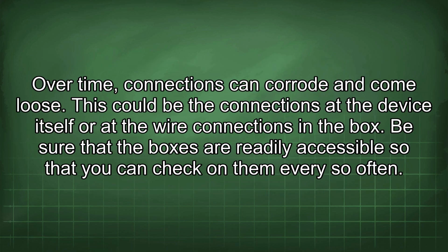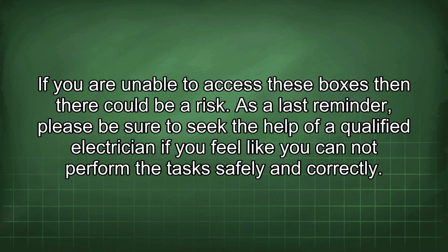Over time, connections can corrode and come loose. This could be the connections at the device itself or the wire connections in the box. Be sure that the boxes are readily accessible so that you can check on them every so often. If you are unable to access these boxes, then there could be a risk. As a last reminder, please be sure to seek the help of a qualified electrician if you feel like you cannot perform the task safely and correctly.